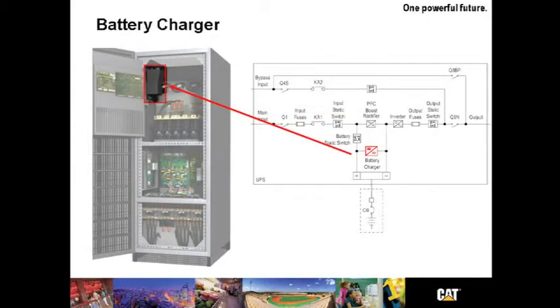In the upper left you can see the battery charger. It draws power from the 800 volt DC bus. Depending on the rating of the UPS, the charger will deliver anywhere from 18 to 50 amps for the purposes of charging the batteries. The charging system is sized to recharge a battery offering 30 minutes of backup time in less than eight hours.